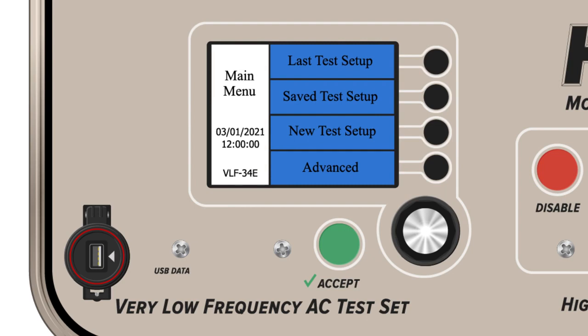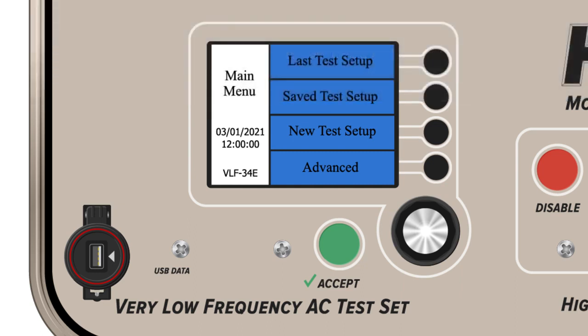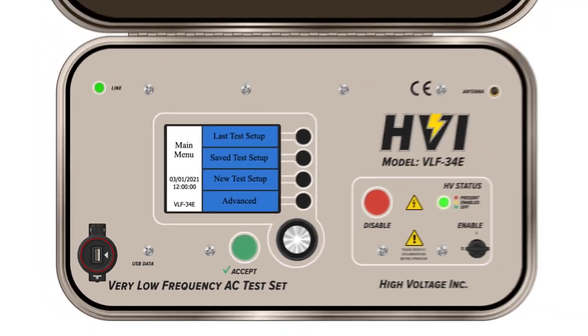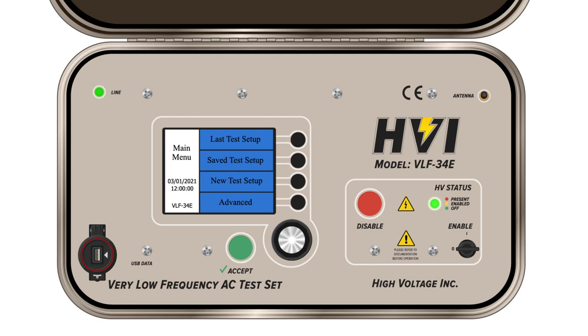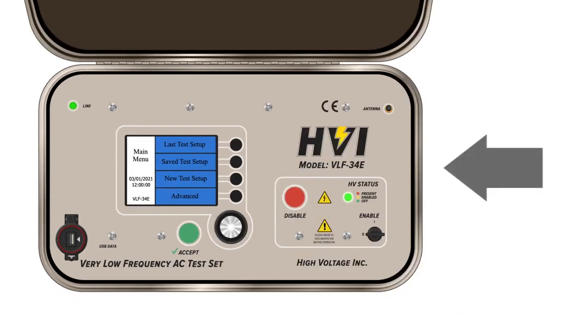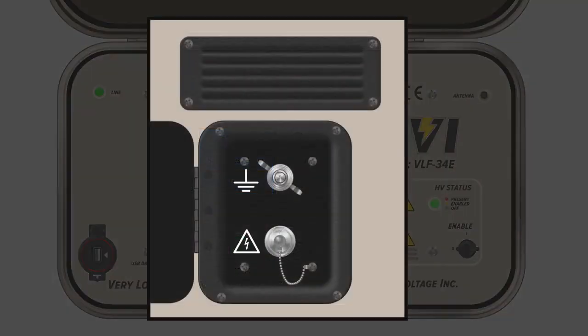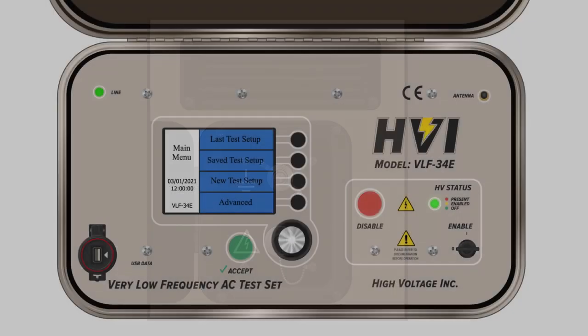Best practices for the VLF E-Series are to transfer saved test results semi-regularly. While there's built-in memory storage, the storage is not infinite, and tests will not overwrite prior saved files when capacity is exceeded. Finally, the VLF E-Series have high-voltage output and ground lead connections. These are housed within the right-hand side compartment case. During a later section of the video, we'll show how to properly set up and connect the high-voltage output and ground lead to these connections.